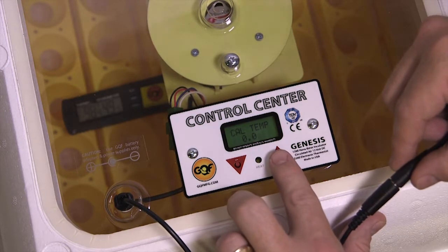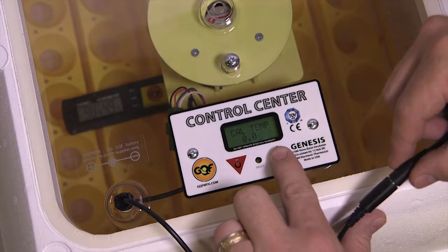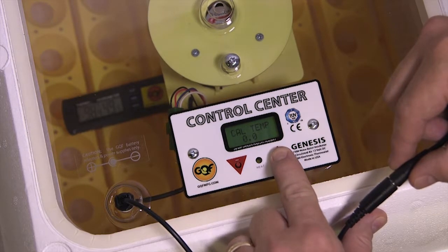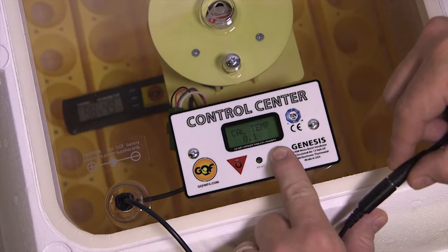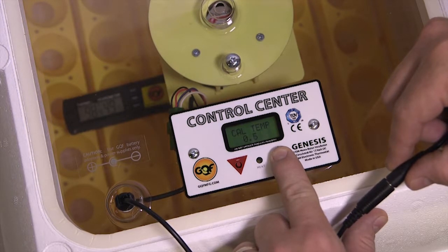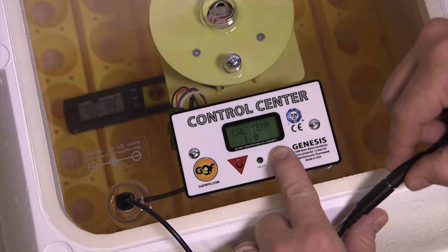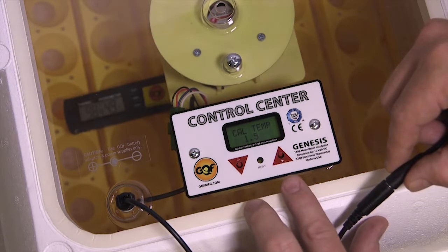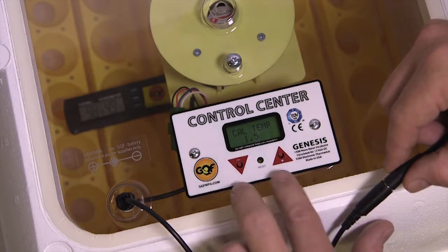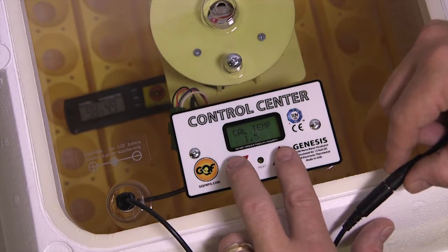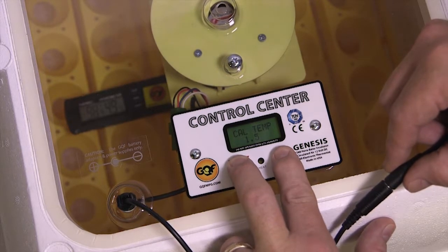I need to add 1.6 degrees, so I hold the up button. And you hold it just for a few seconds and it'll start to move. I'm going to stop it at 1.5 right there. Okay, so that's going to add temperature to the incubator. And then to advance to the humidity screen, I'm going to hold both buttons and release.